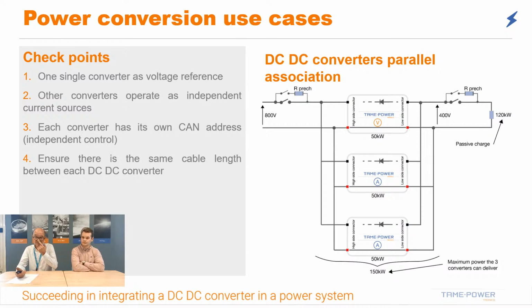The case represented here is one where one converter determines the voltage. The top converter will determine the voltage, and the second and third converter will add additional current just to reach 50 kilowatts each, acting as current sources. So this is a way to connect several converters in parallel even if you want a voltage source on the output — the output voltage is determined by the first converter, and the additional current is brought by the other converters.